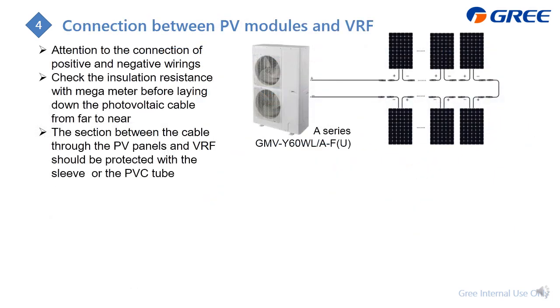Next is the detail of how to do the wirings, and this example is for this model. After you do the wirings of the PV panels, just pay attention, don't mix the positive and negative. And also check the insulation resistance with the megameter before laying the cable down. And also this cable will require protection.